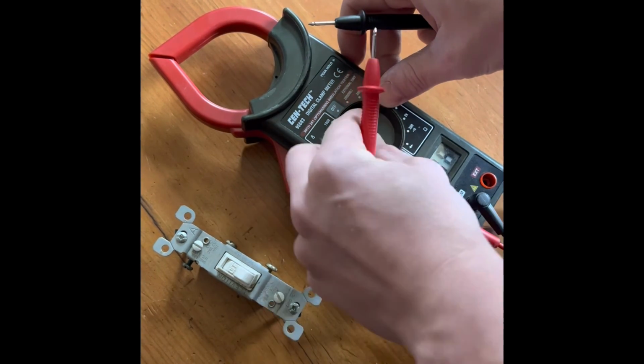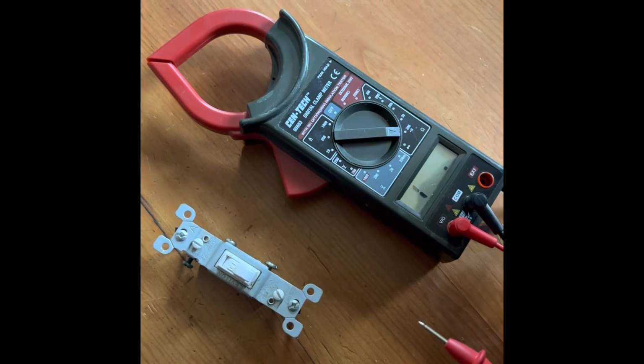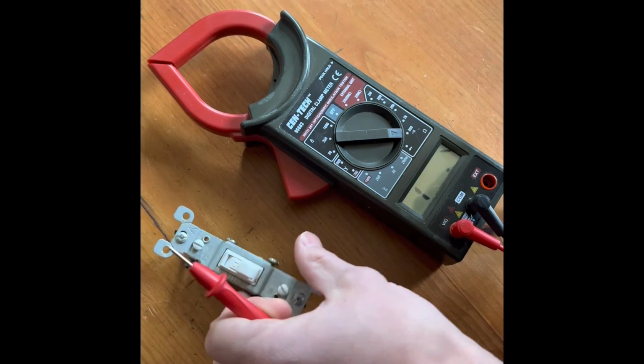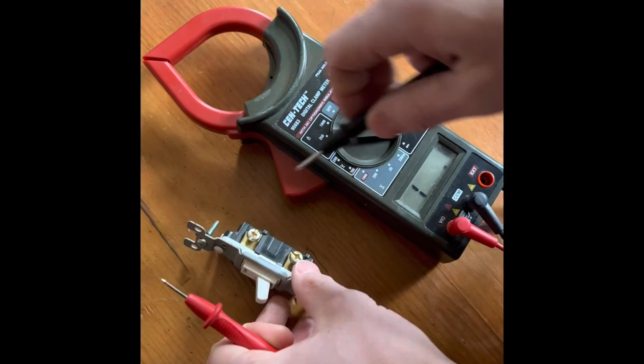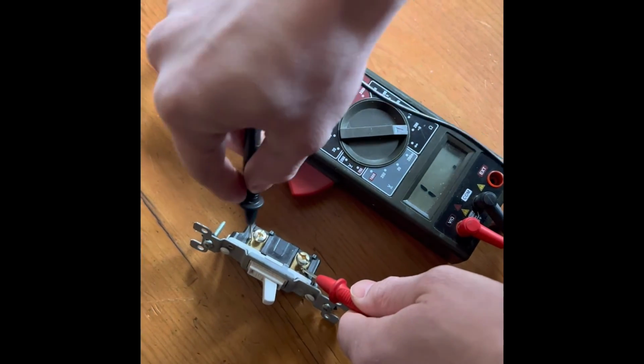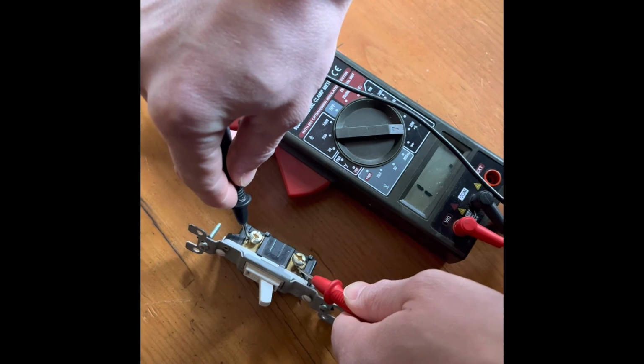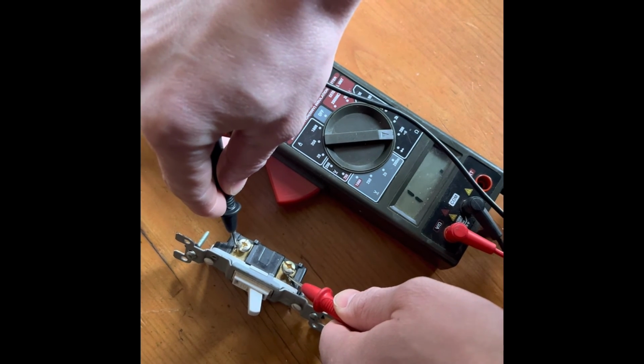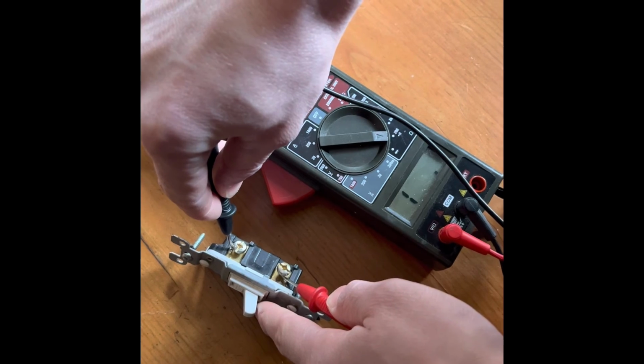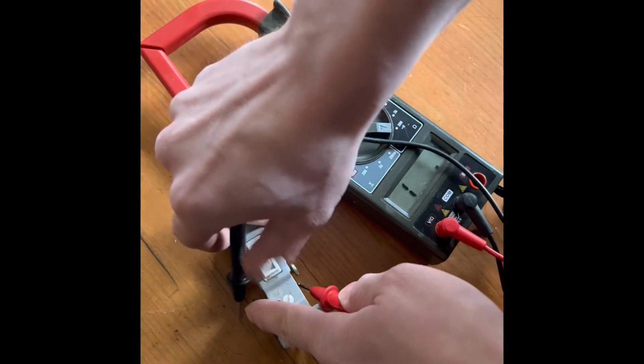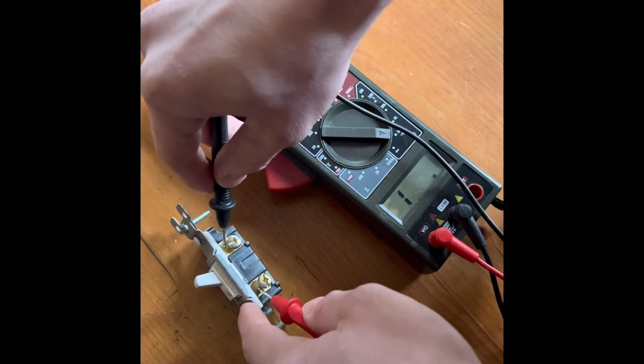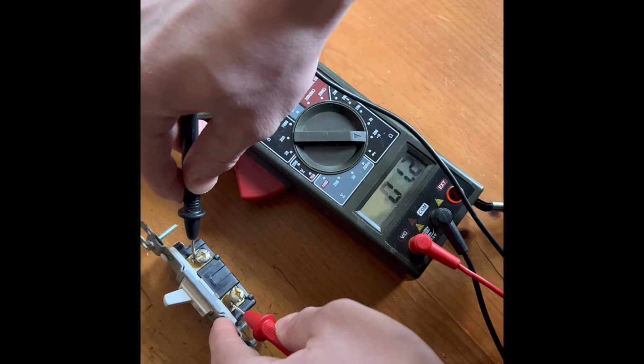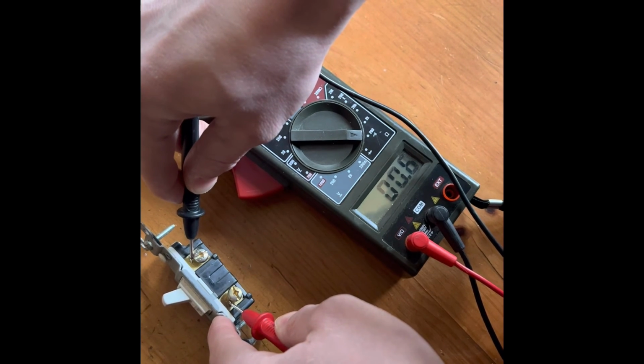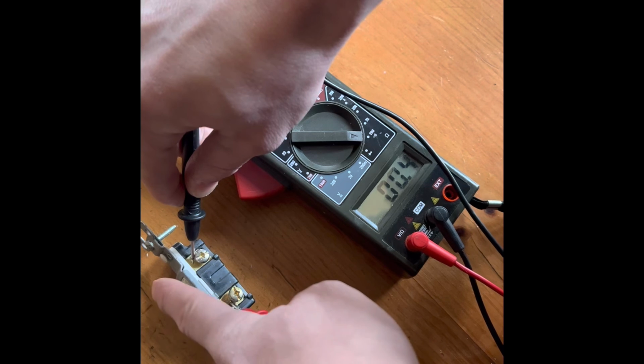I'm going to put my ohm meter to 200, and I'm going to test the switch while it's off. And my reading is 1, which means that the switch is off. When I flick the switch on, I get a reading of just under 1, which tells me that my switch is working properly.